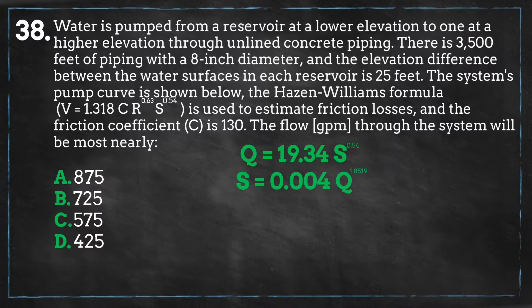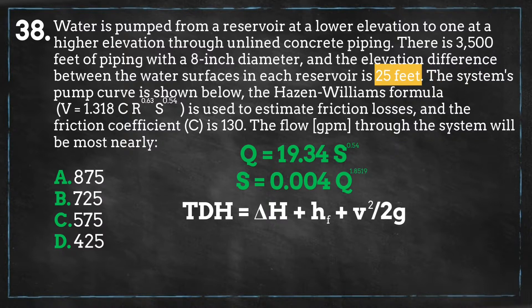The TDH we will be solving for to place on the pump curve equals the following: where delta H is the difference in elevation, H sub F as mentioned earlier equals the head loss, V equals the flow velocity, which is equal to the flow rate Q divided by the pipe's cross-sectional area, and G equals gravity, which in US customary units equals 32.17 feet per second squared.